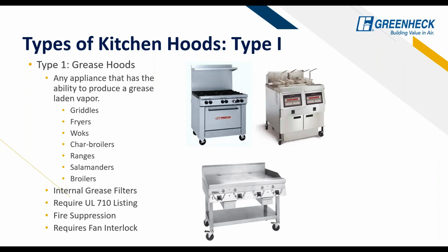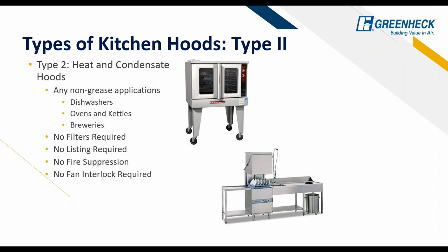Typical appliances for this are griddles, fryers, charbroilers, anything you might see in a burger restaurant, stuff like that. You also require that UL 710 listing as well. And then type 2 is really just for heat management. There's no listings required with these, no filters and no fire suppression. And there's also no fan interlock required. We'll get into a little bit of the controls later on, but that is one of the distinguishing factors as well.